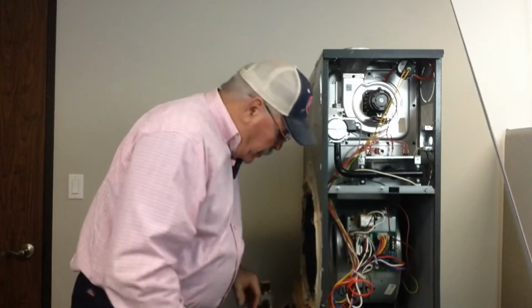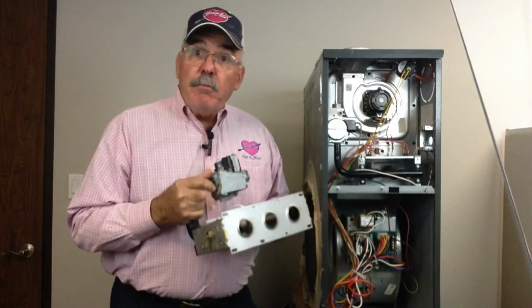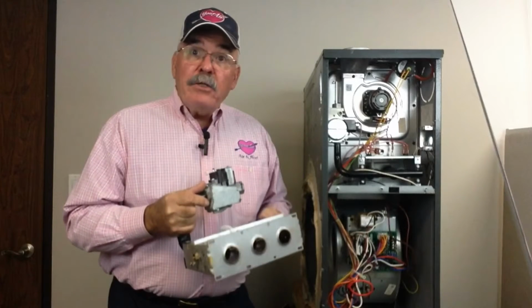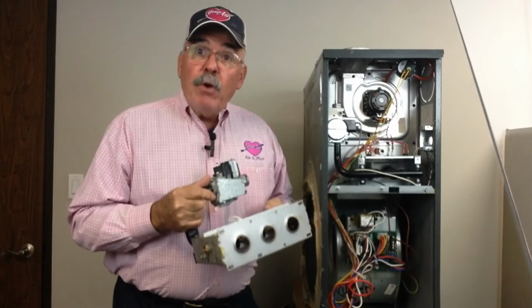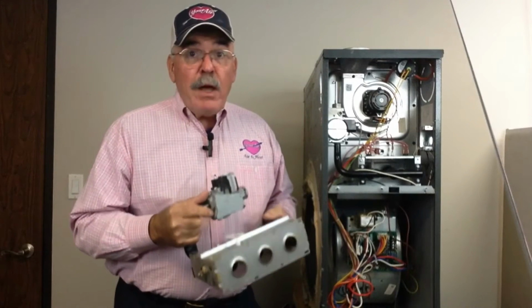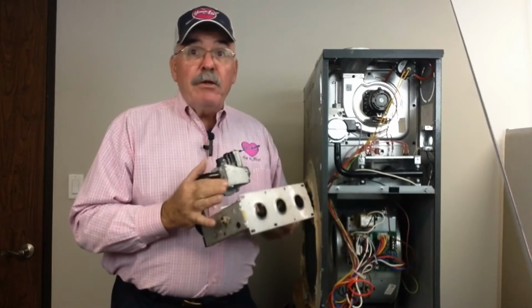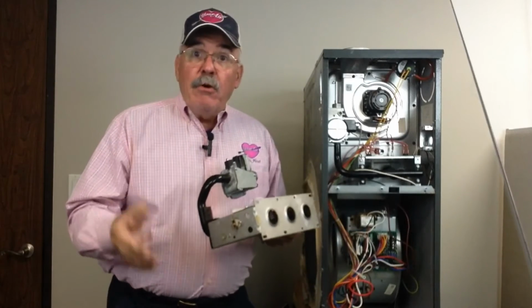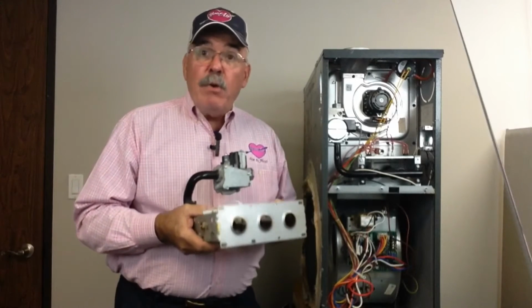from a technician. Now, while that chamber is open, your burner assembly, which looks just like this, should be pulled and checked to make sure that the burners are operating correctly and burning cleanly, so no excess carbon monoxide is being formed during the burning process. If the burner assembly is found to be corroded, corrective action has to be taken as well, and the burner ports in here have to be cleaned of all the corrosion, because if there's too much corrosion at the end of these tubes, it can cause the openings to close and the burner's going to fail, which won't let it ignite, and it'll cause you to have no heat in your home.